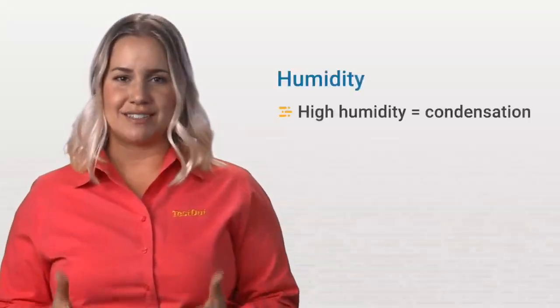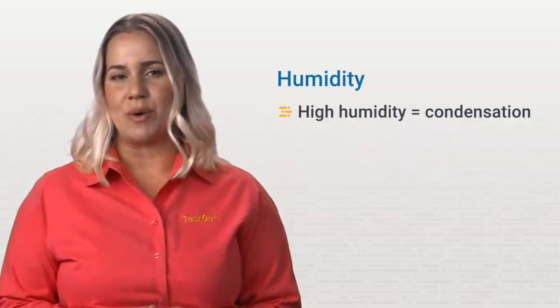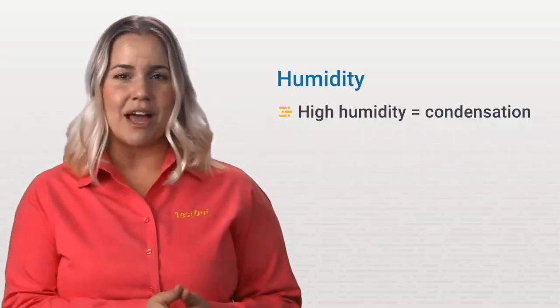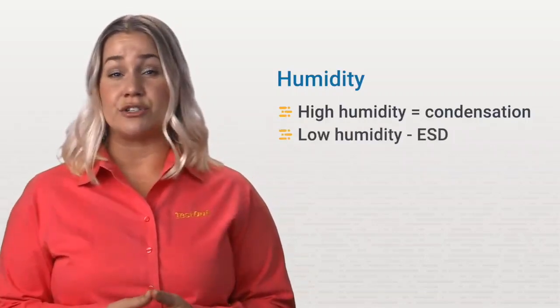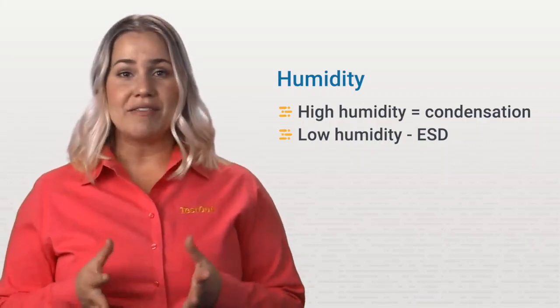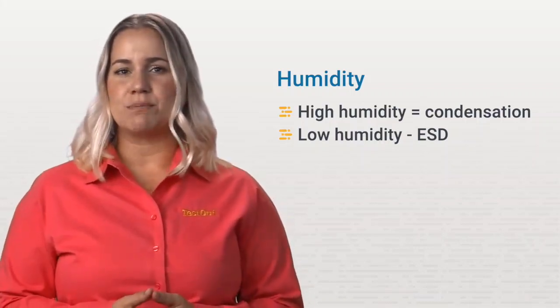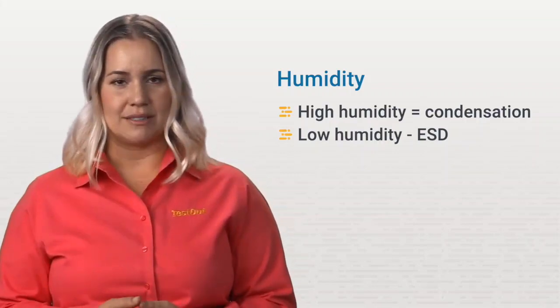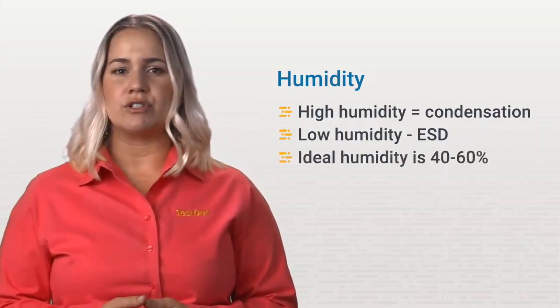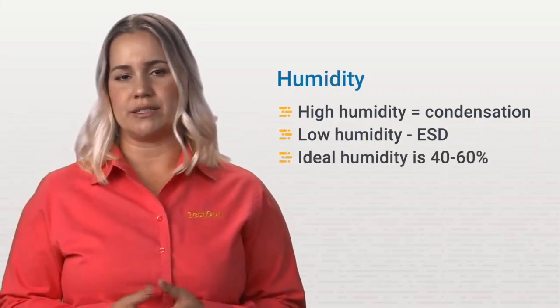Computer systems don't function well with too much or too little humidity either. Computers are designed to operate within a humidity range, so you need to monitor the humidity within your organization. Too much humidity results in condensation, which is bad for electronic equipment. Too little is also bad because electrostatic discharges are more likely. The drier the air, the more easily static sparks can jump and damage components. The recommended humidity level is usually around 40 to 60%.